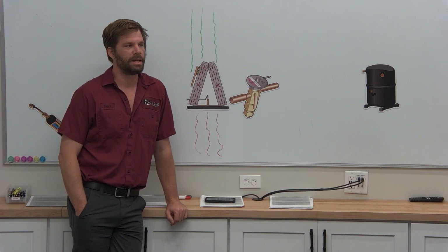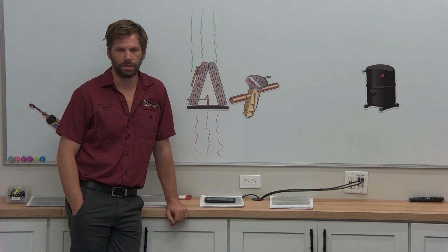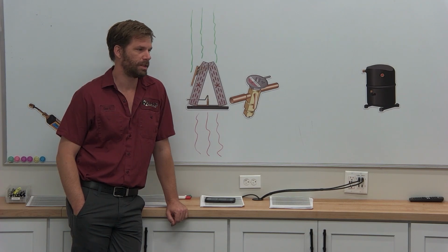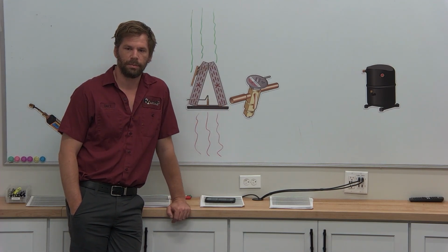And so investigating what could have changed, if this is a new thing, that's part of your diagnostic process on the job. If this is a new system, a new setup, whatever it is that could have changed. Maybe there normally is a 4-inch filter in and now there's no filter in. You look at something like that could dramatically change the airflow.